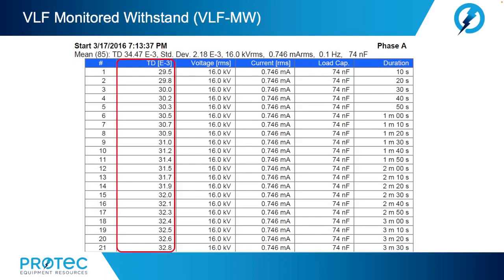We also see that the tan delta values during the time period start to increase even though the voltage is fixed at the 16 kV withstand test voltage level. We are now clearly beginning to witness the growth of a defect channel. Now, the benefit of the withstand test is as we see the deviation grow or we begin to see the tan delta grow, we can either immediately stop the test before changing the as found characteristics of the cable, or we grow the channel during the duration of the test into a defect where we can now locate and render the necessary repairs.